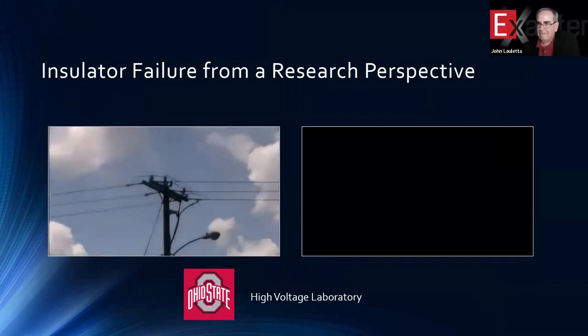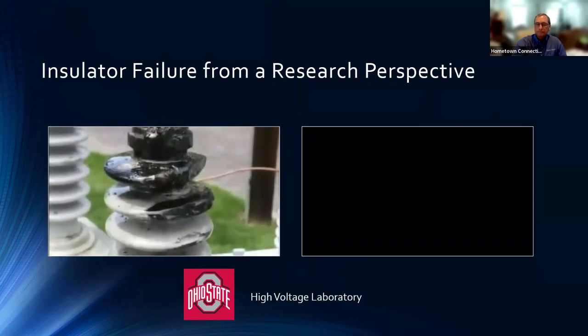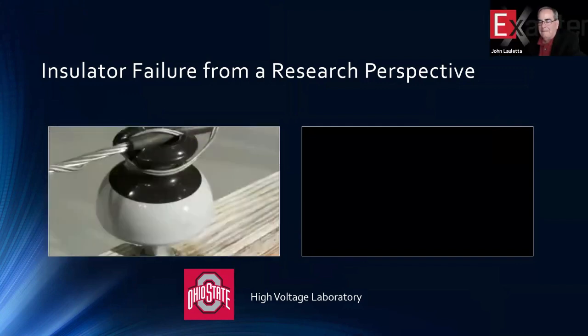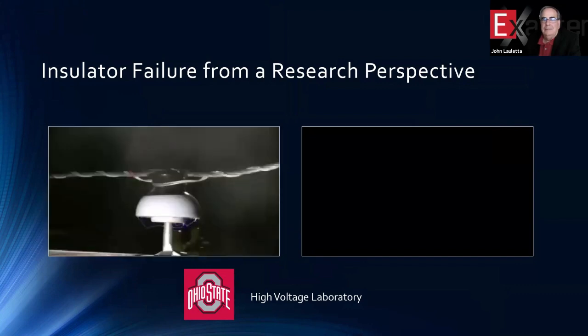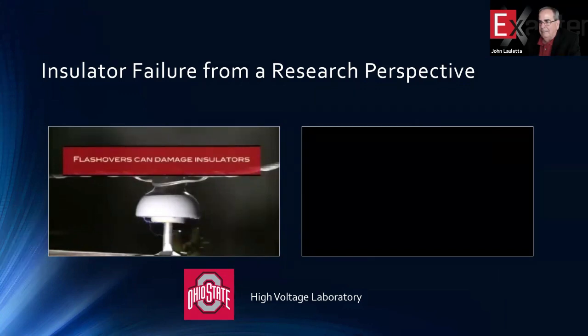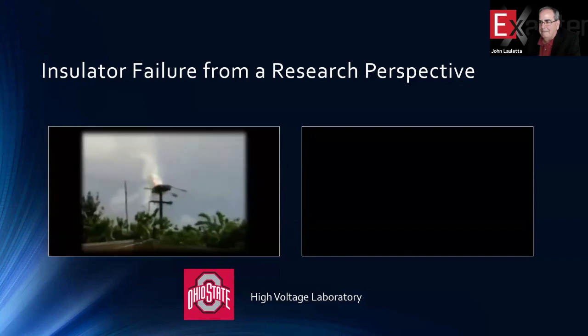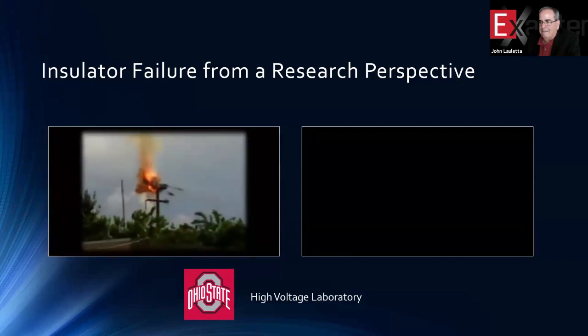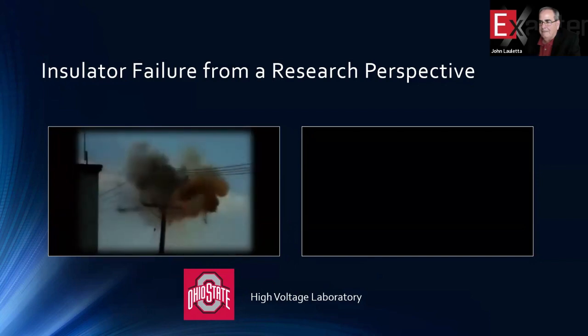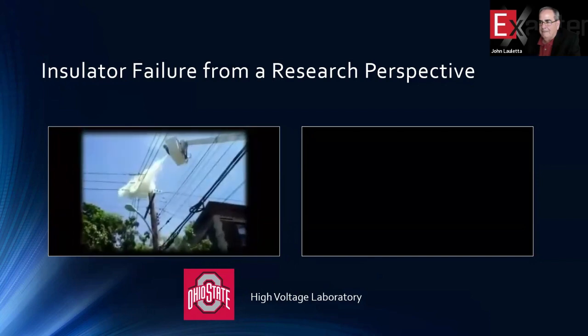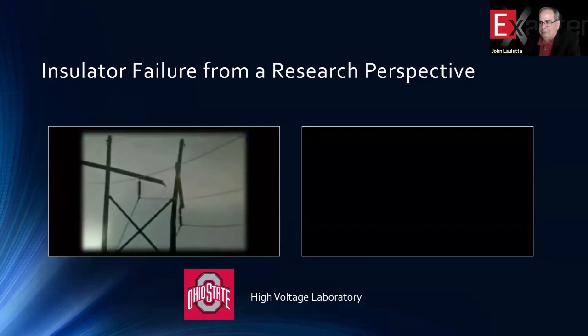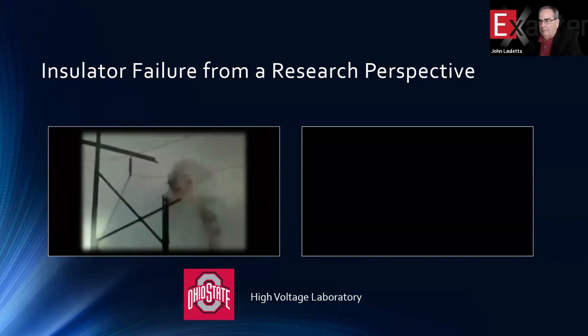Sometimes utilities will notice insulators that are damaged, even melted down. Professor Sibo shares on this, that if the protection is not quick enough and the flashover is there, it could damage the insulator itself. And this is why you can see melted sections of the conductor tie wires, suspension insulator caps. The heat factor of scintillating insulators is another issue. Leaking or arcing insulators are continuously releasing heat into the wood poles, which over time can cause pole fires, broken poles, and create significant line and circuit damage.